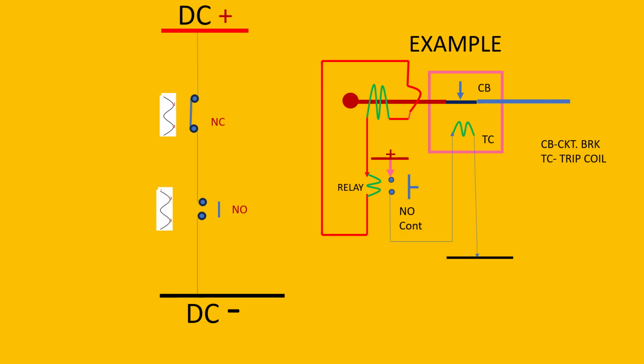I have shown these two types of contacts in the drawing, and this is shown in this way. Now I'll show you how it operates. Friends, in the picture, both the contacts' electromagnets are in de-energized condition, and in this condition one contact is closed, that is normally closed, and one contact is open, that is normally open. Now see, if I energize the normally closed contact magnet, it will open, and if I energize the normally open contact, then it will be closed.